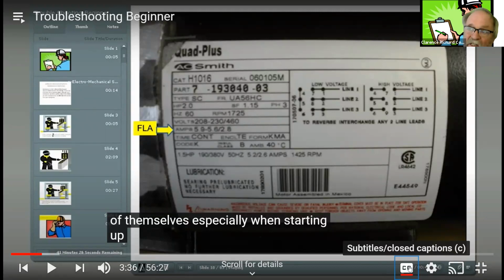Then you notice that this is a 2 horsepower, 3-phase, 60 hertz, RPM 1725. Volts, we have choices of volts. We got 460 volts or 230 volts. On the right side, it shows you how you can wire up to the low voltage, which is the 230 volts, the 208. High voltage is going to be the 460.